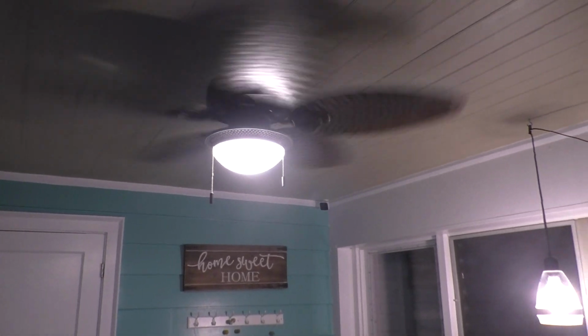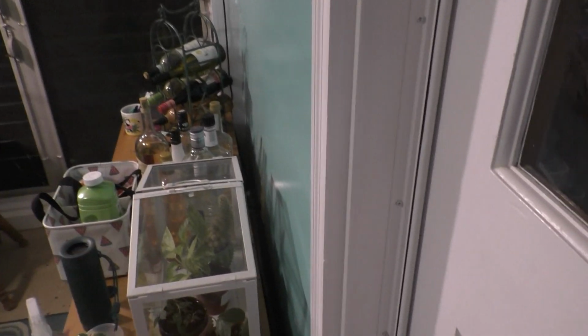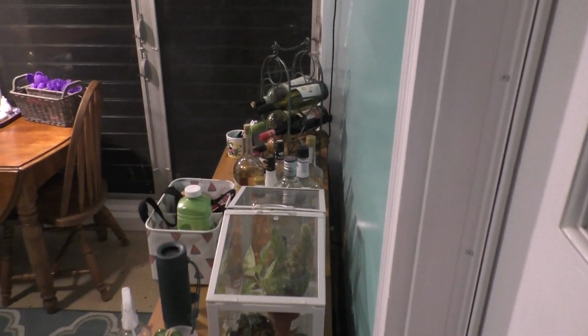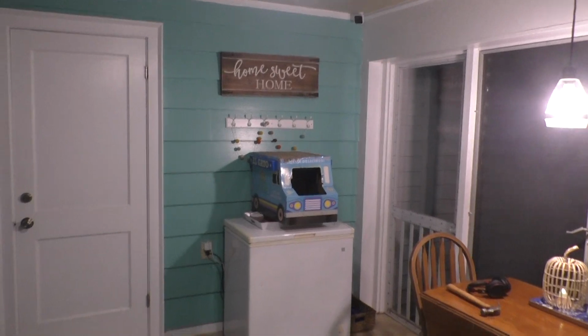So step one, we took that switched outlet and we made it a standard outlet. We actually pulled the wire out, put a pull string behind the wire, and that outlet is now wired into the Breezeway circuit. I added a circuit to the breaker a couple years ago just for this room, a 15 amp circuit. So that's now powering that outlet, and it daisy chains off into that outlet, where it then springs off to the garage lighting, which is how I had originally wired it.